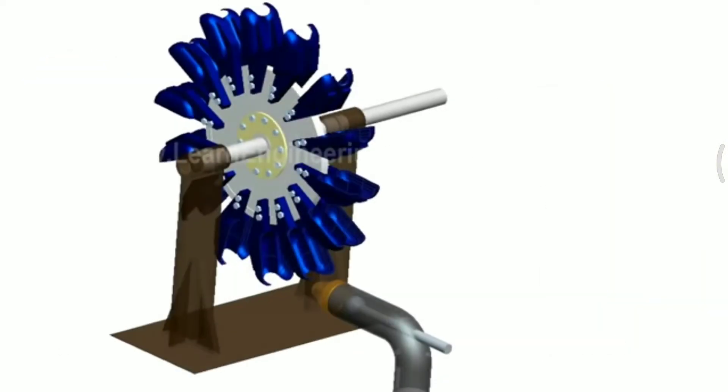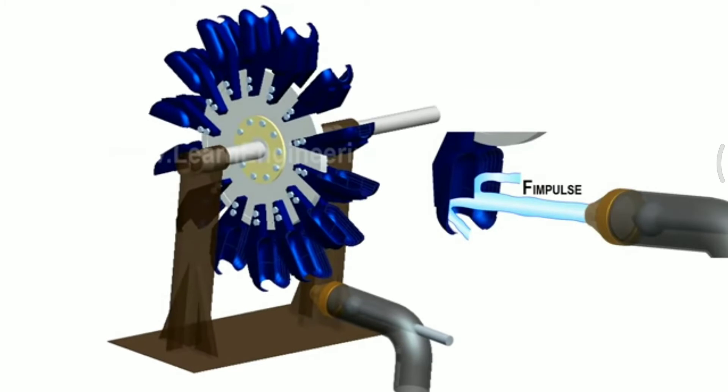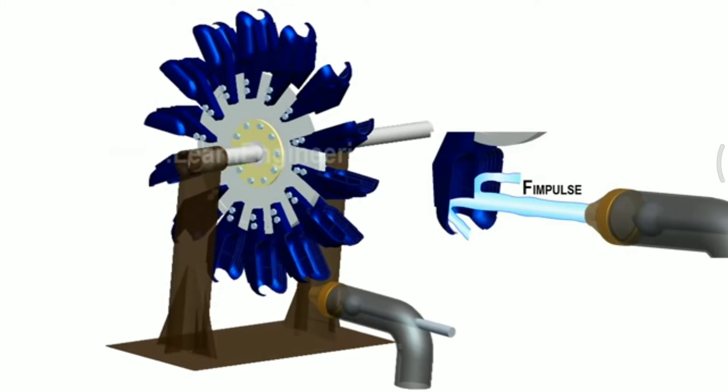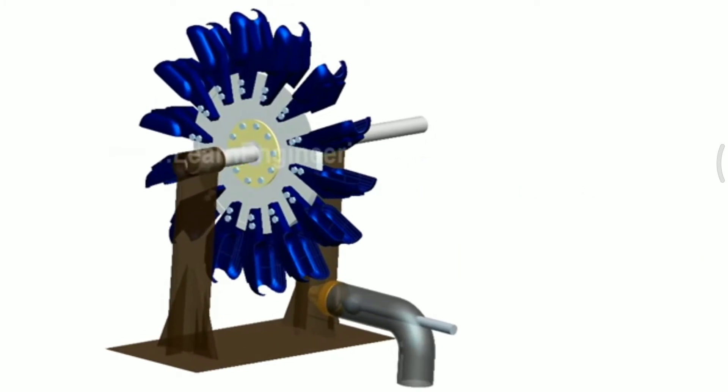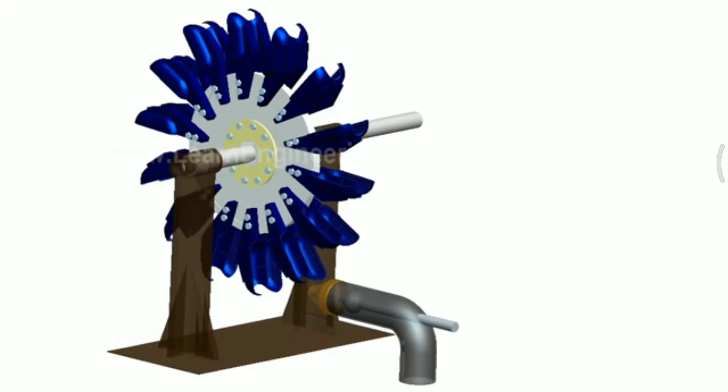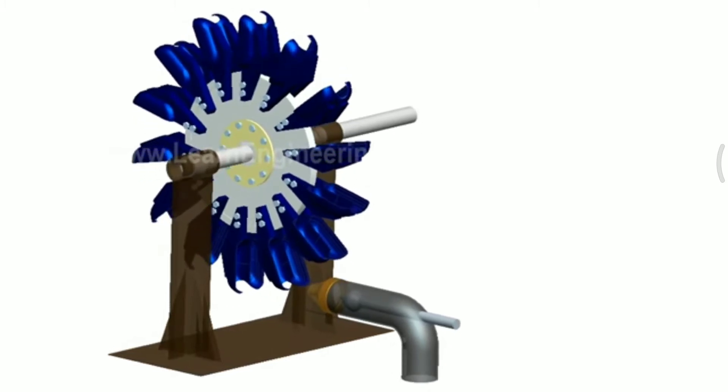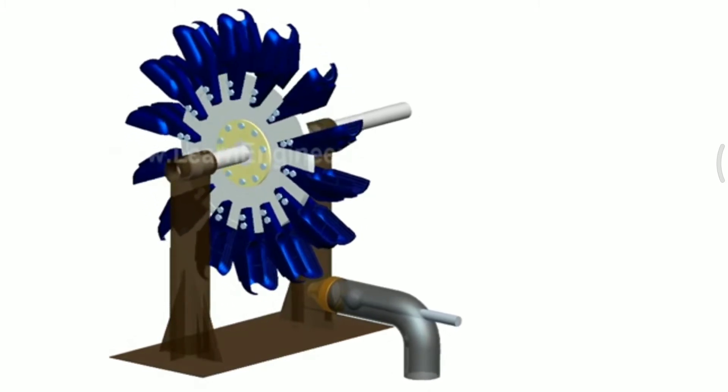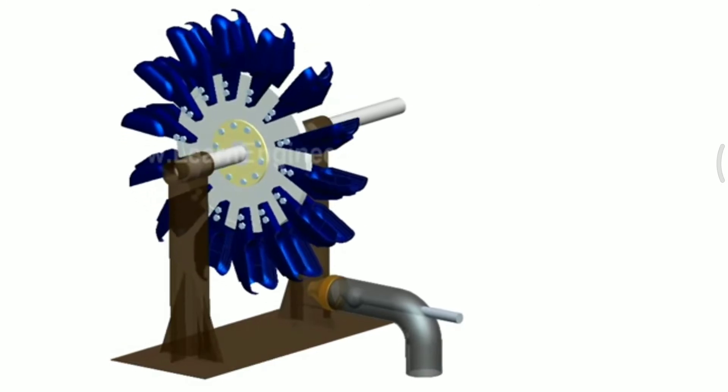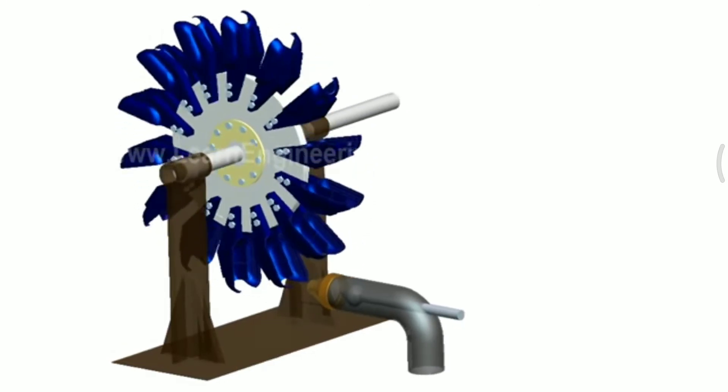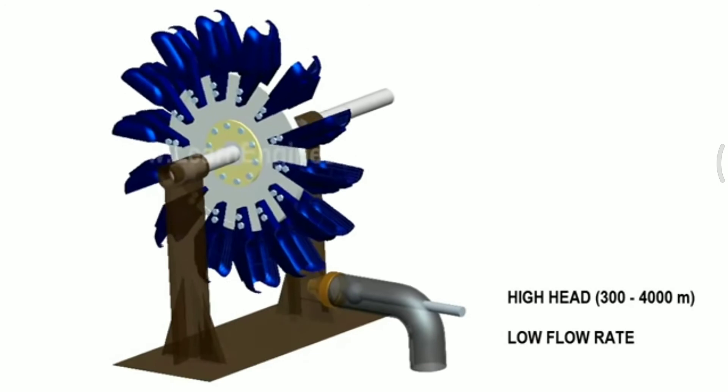In Pelton, pure impulse force of water jet is responsible for rotation of impeller. Water stored at high altitude can produce high impulse force due to its high velocity. So Pelton turbines are suitable for operation when water energy is available at high head and low flow rate.